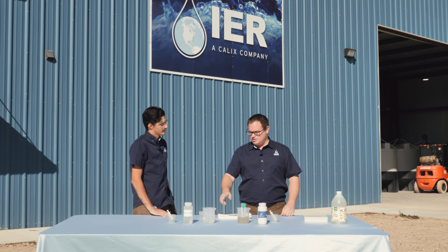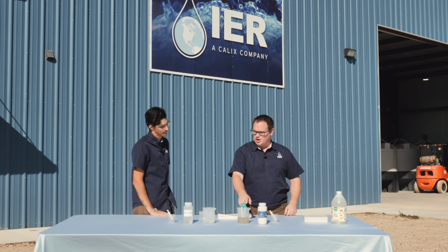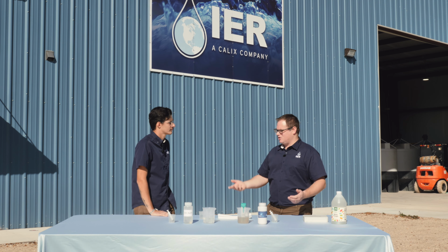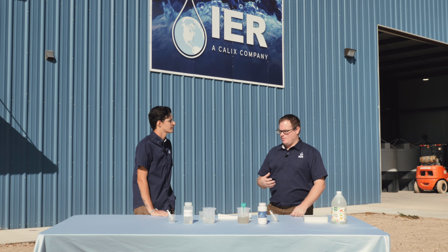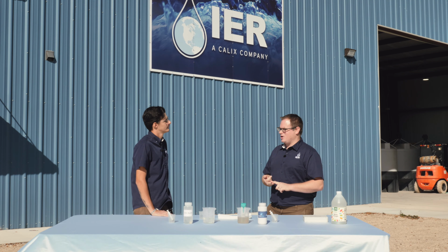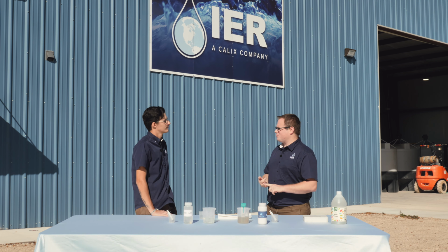But one thing we did notice, caustic soda was very instant. Magnesium hydroxide took 15 or so minutes to reach that. So that's the difference there, the reactivity time. But because of that reactivity time, there are other advantages that you see. We see the safety of the product. It's a safer product to handle. It is also a better product for a treatment facility, as it provides some alkalinity. It also works better in collection systems because of that buffering capacity.